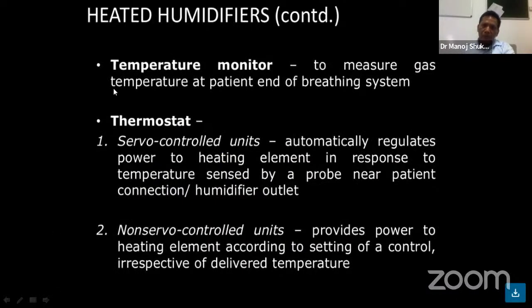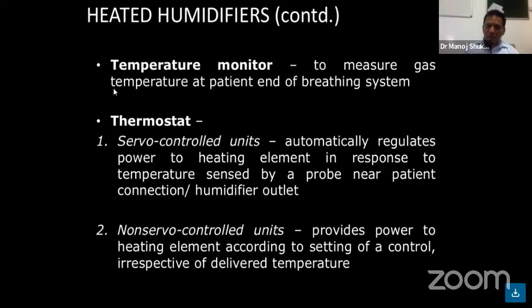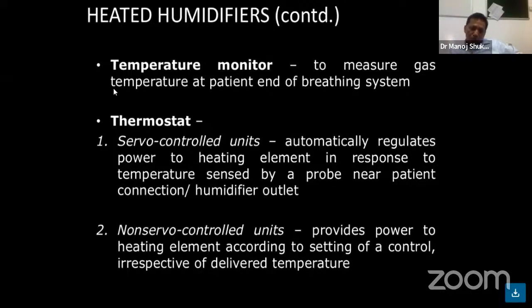In heated humidifiers, we have a temperature monitor to measure the gas temperature at the patient's end of the breathing system. There are two kinds. First is the servo-controlled unit, which automatically regulates the power of heating elements in response to the temperature measured near the patient's connection. Second is the non-servo control unit, which provides power to the heated element according to the control setting, irrespective of the delivered temperature.